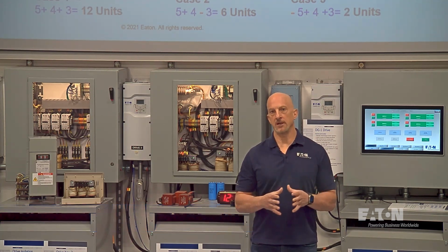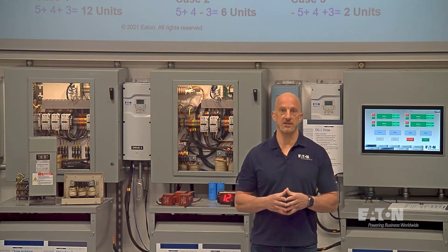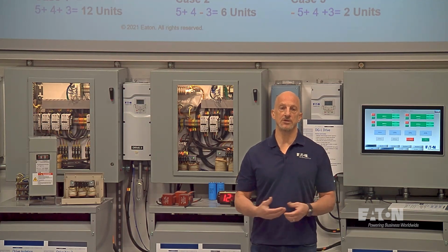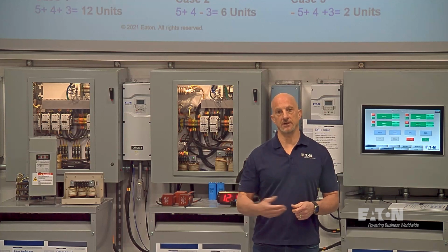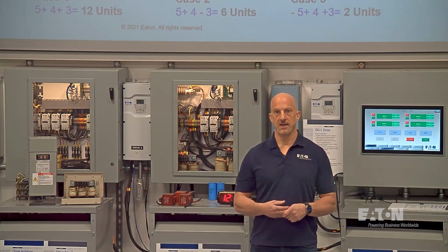So harmonic mitigating transformers can be used strategically throughout a system like that to really reduce the harmonics that you see. And then you don't need harmonic filters or other things added on after the fact.